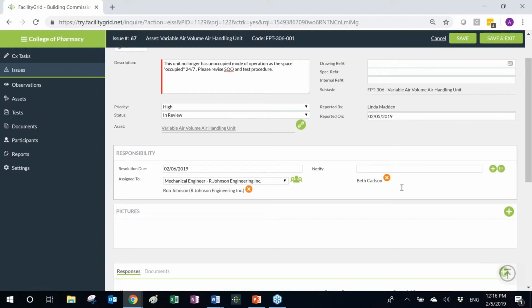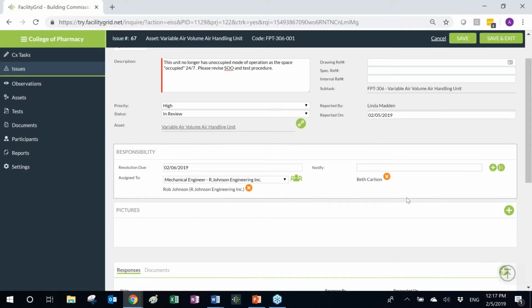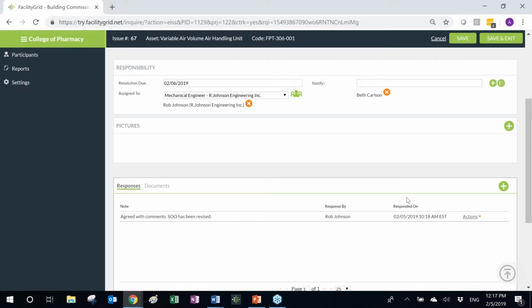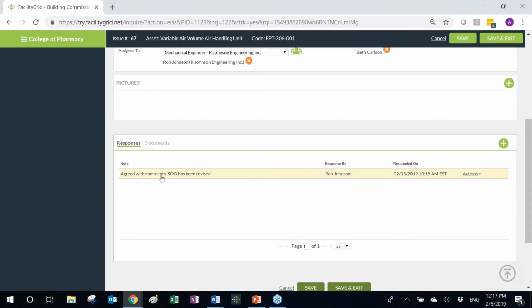So I may decide to include a commissioning agent as the person to be notified on this issue. So the commissioning agent understands that there's an issue on this test that has to be addressed prior to conducting the actual functional performance tests. And again, the reason is because we want to conduct the functional performance testing only once the testing procedure is aligned with the sequence of operation, and when both are aligned with what has been programmed. Now, the engineer of record receives a notification of this particular issue and then enters their response. So in this case, the engineer of record logged into the software and indicated that they agree with the comments and the sequence of operation has been revised.